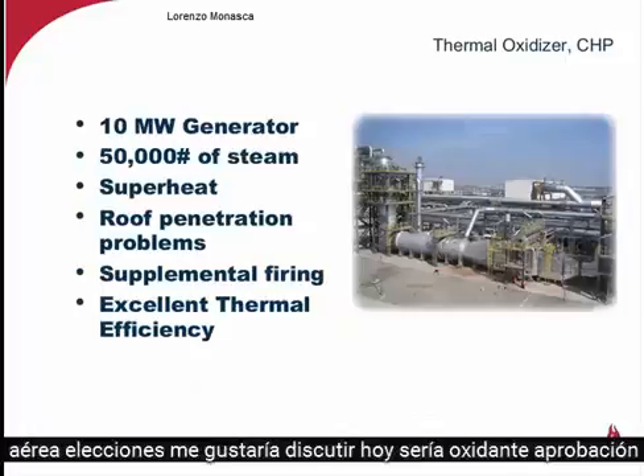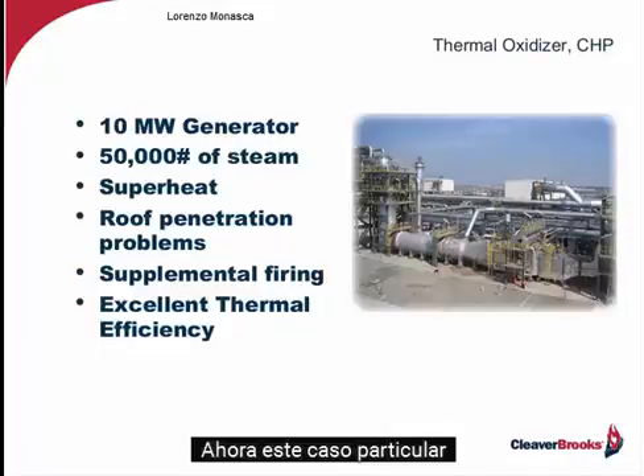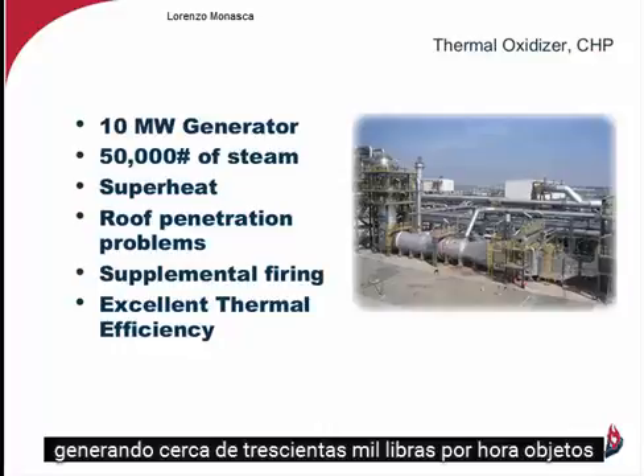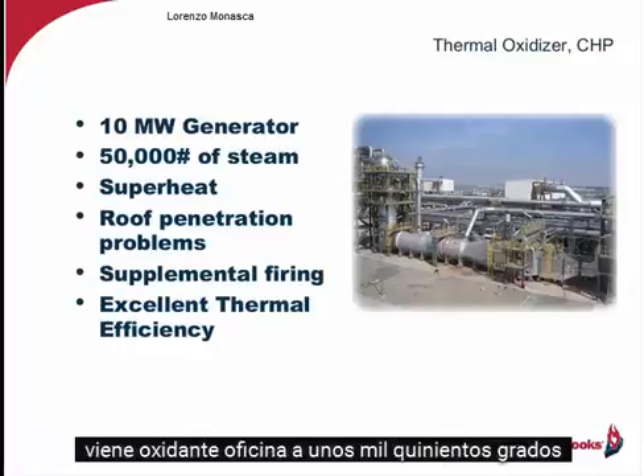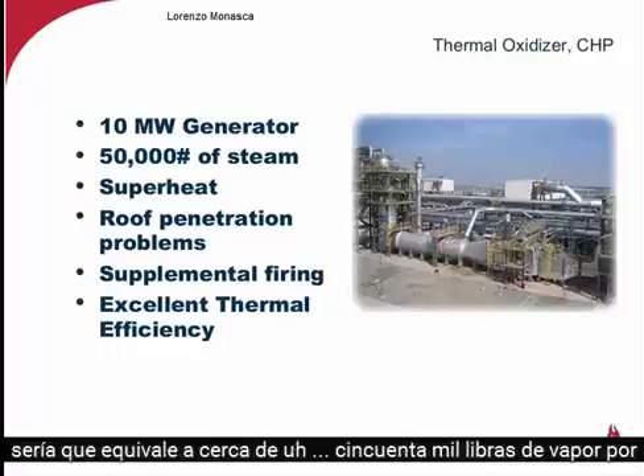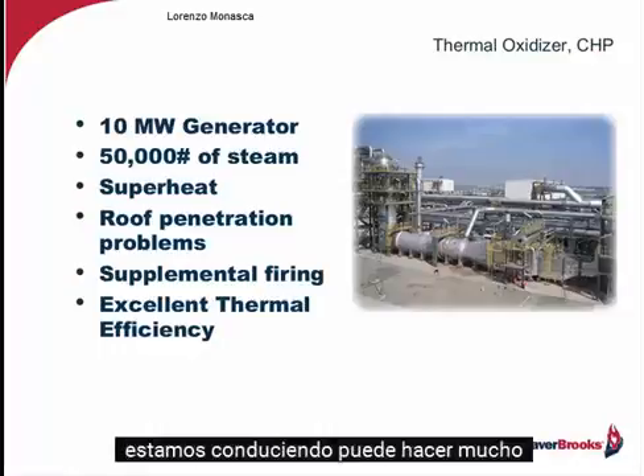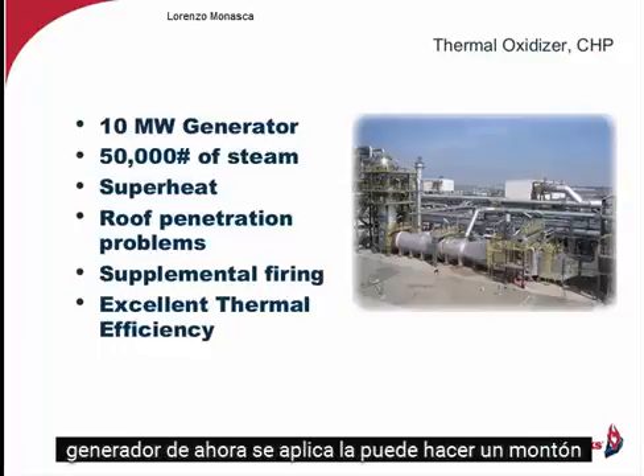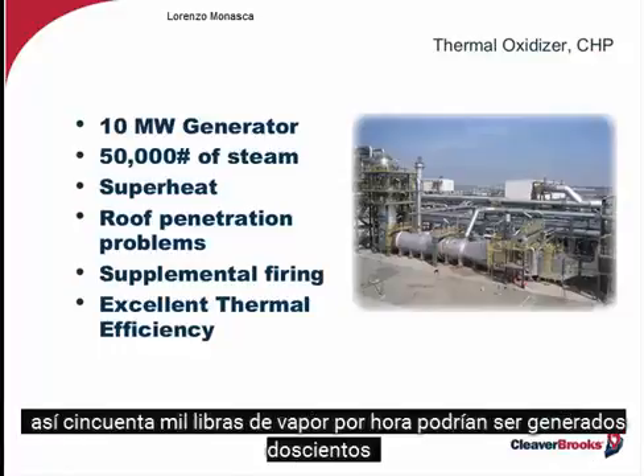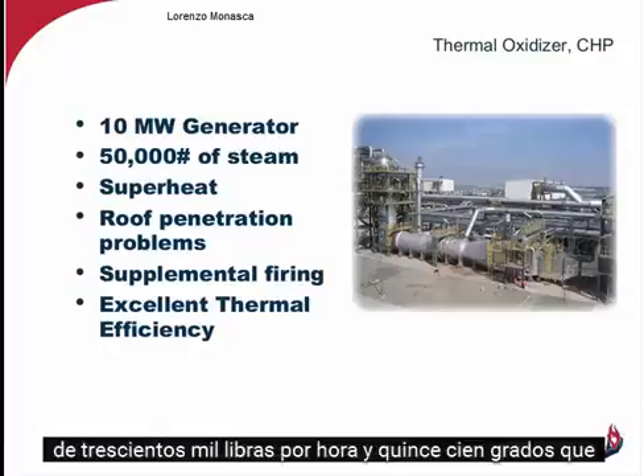Now, the next scenario I'd like to discuss today would be a thermal oxidizer. In this particular case, we've got a thermal oxidizer that's generating about 300,000 pounds per hour of gas coming off this oxidizer at about 1,500 degrees. That's equivalent now to about 50,000 pounds of steam per hour. We're driving a 10 megawatt generator now, not a 5, but a 10 megawatt. So 50,000 pounds of steam per hour could be generated at 200 pounds with that mass flow of 300,000 pounds per hour and 1,500 degrees. That's what we could generate.